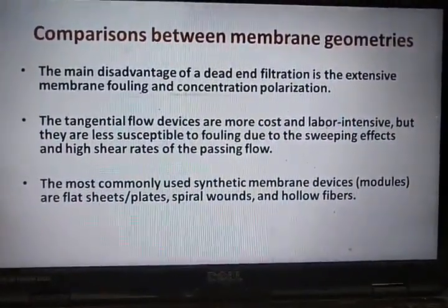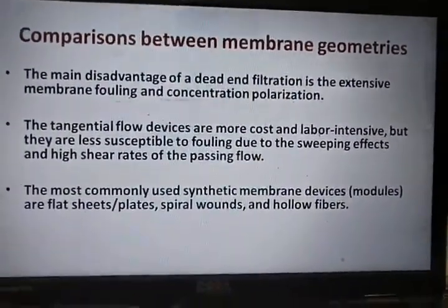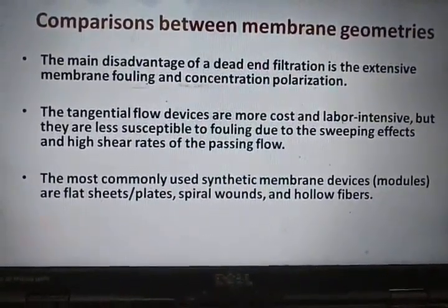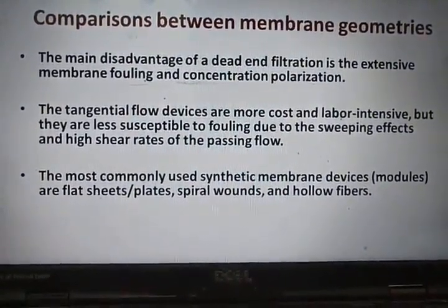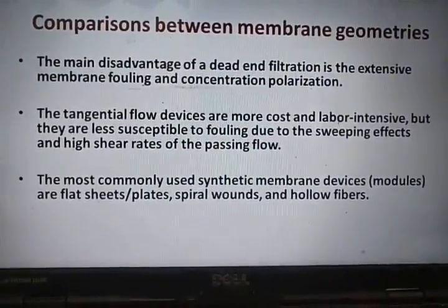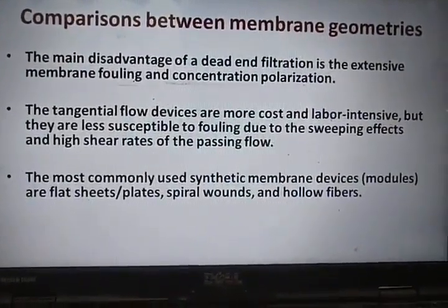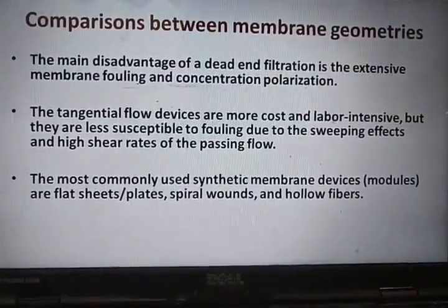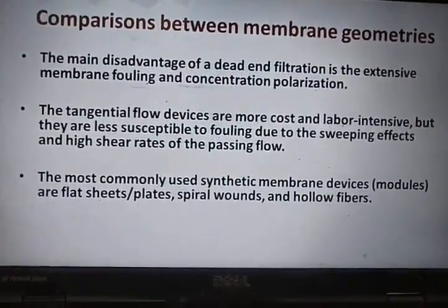Comparison between membrane geometries. That means based on the applications we can select the appropriate membrane configuration. Here the main disadvantage of dead end filtration is the extensive membrane fouling and concentration polarization. So we will talk more about membrane fouling and its prevention in the subsequent slides. As of now, just understand that membrane fouling is a process by which the performance of the membrane is reduced due to the deposition of impurities onto the membrane.